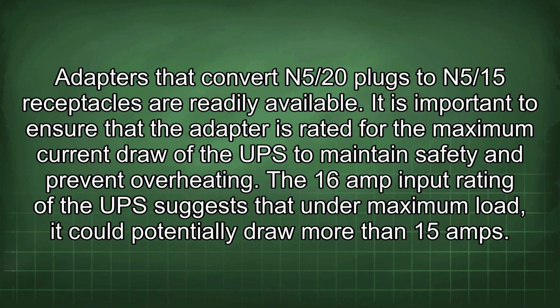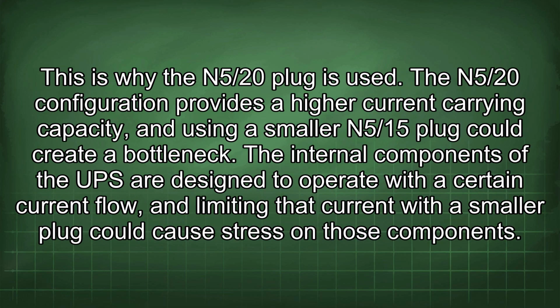safety and prevent overheating. The 16 amp input rating of the UPS suggests that under maximum load, it could potentially draw more than 15 amps. This is why the N5/20 plug is used. The N5/20 configuration provides a higher current carrying capacity, and using a smaller N5/15 plug could create a bottleneck. The internal components of the UPS are designed to operate with a certain current flow, and limiting that current with a smaller plug could cause stress on those components.